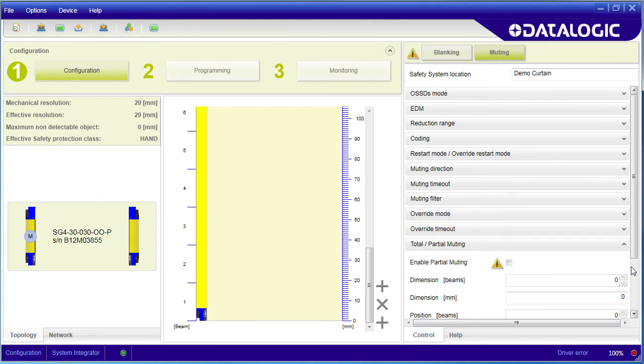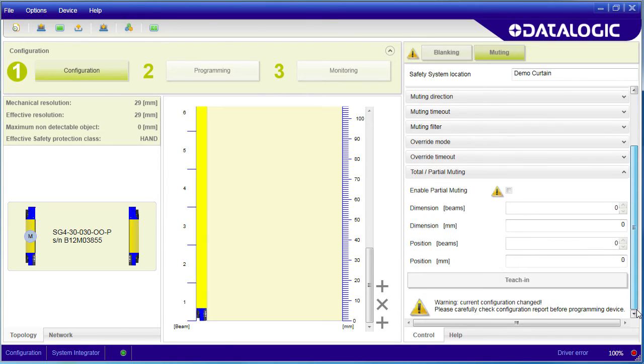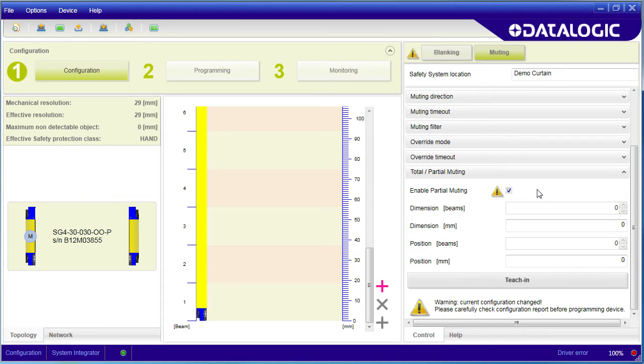Normally, the entire light curtain is muted when the two muting inputs are sequenced correctly. You can also specify that muting only affects a portion of the light curtain. Maybe boxes on a conveyor only use the bottom third of the light curtain.